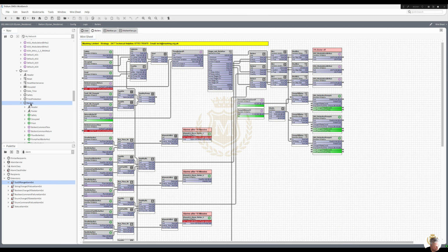Boilers. So I wrote this from scratch, couldn't be bothered to copy anything across, found it easy just to write it from scratch. Safety, occupied, frost. So we've got the safety in occupied, and with this I've basically put it so that the pumps are running. So I'm checking that both pumps are healthy, or at least we've got one pump healthy, and we've got flow on one pump. Once we're happy with that, then we can actually go. The same with the frost. It's still using the safety and the frost, and then still the same 2 at the bottom there. We can go. So one or the other, we can start that loop running.